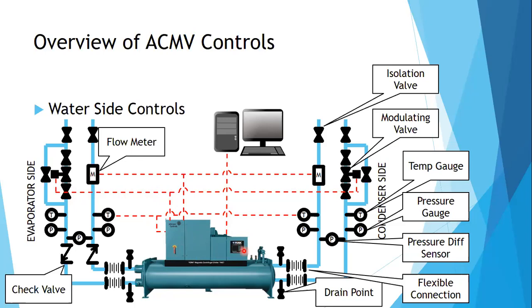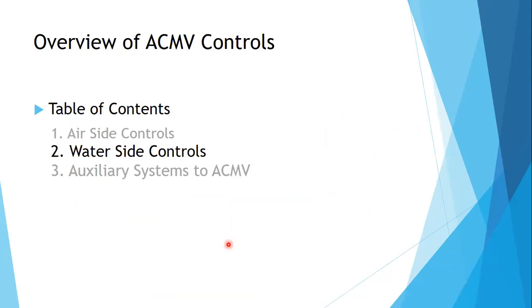Your chiller will know. And this chiller, like what I said, is controlled by proprietary software, and they are connected to each other also. So this chiller would know if the other chiller is running at 100% or if it's also running at 75%. Okay. So that's it for our waterside controls. We have learned how to control our air handling units, or our airside, and we have learned how to control our waterside. So this is the control of your ACMV.